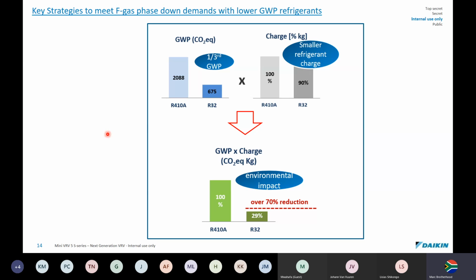So if we look at the key strategies to meeting F-gas phase down demands with lower global warming potentials, here they say the global warming potential, I was a bit out with my figures, R410A is 2,088. So you lose 1 kilogram of R410A, it's equivalent to 2,088 kilograms of carbon, whereas you can see R32 is much lower.